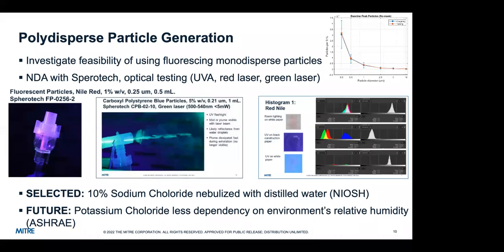But at the time, we decided not to go that way, but to use sodium chloride, 10% sodium chloride in air. That's because it's a NIOSH standard that's often done, and if you're going to have people around, sodium chloride in air is probably the safest thing you can put into the air system. So that's what we looked at. But it's still a good consideration, especially if you want to test something out - somebody might want to go back and take a look at that.